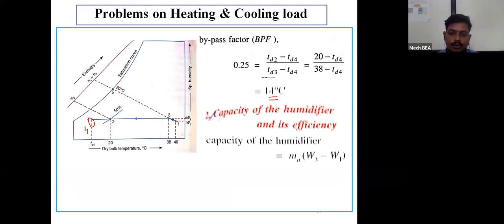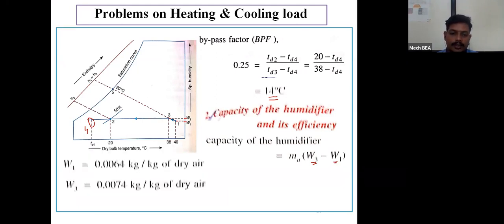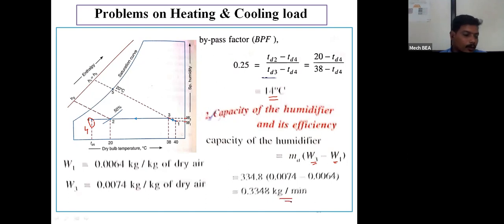The specific humidity difference to be taken is that between point number 3 and point number 1. Which value is higher? W3 is higher than W1. So put W1 and W3 as 0.0064 and 0.0074 kg per kg of dry air. By putting those values, I will get the capacity of humidifier, in terms of kg per minute.